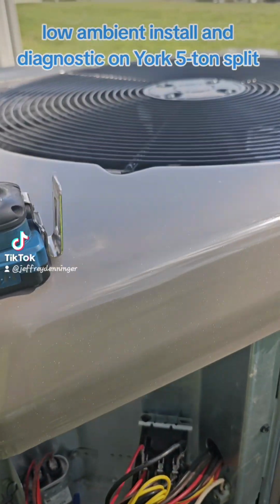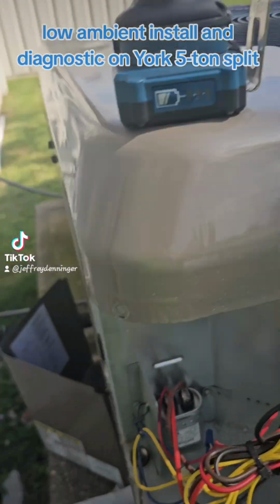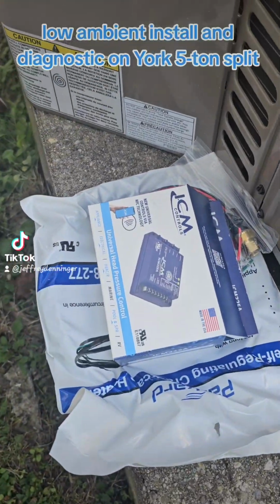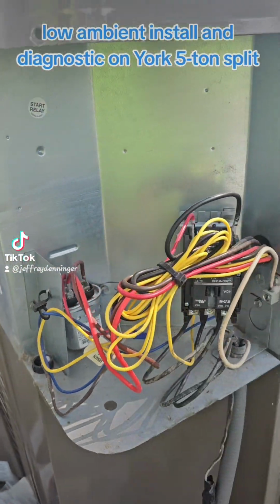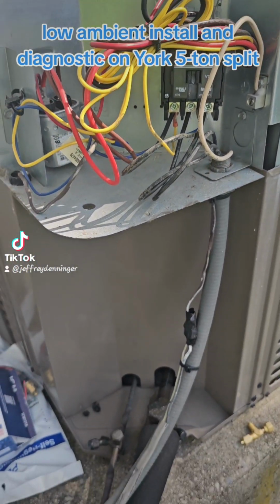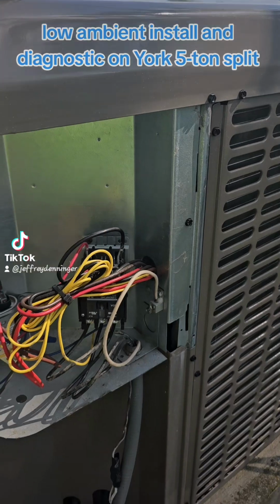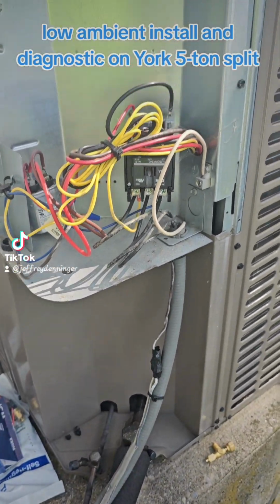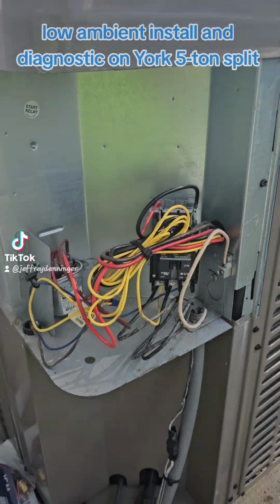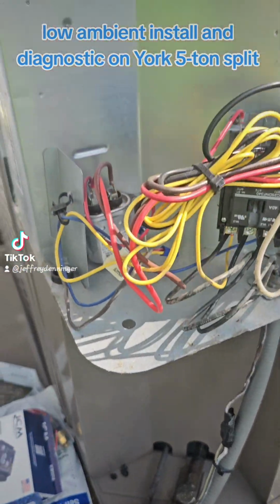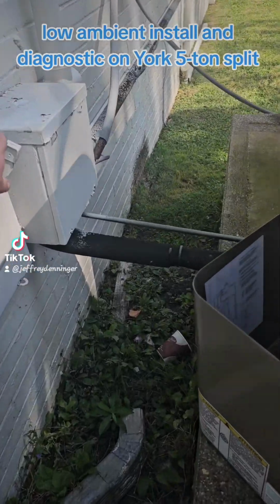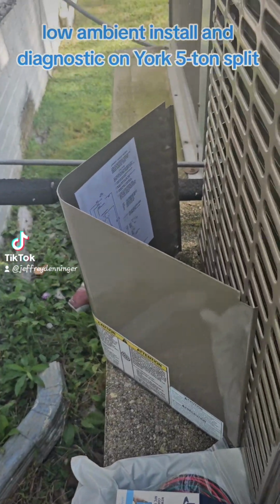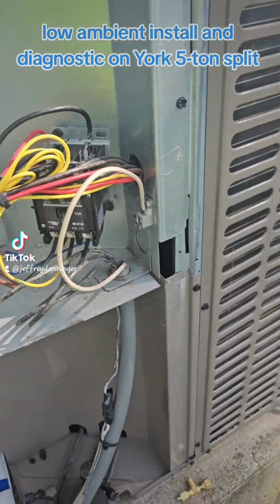Okay, today we are taking this outdoor condensing unit and we are installing a low ambient kit in it so that the customer can use it when it's cooler outside in the evenings and not freeze up the coil like they did the other day. So first thing I'm going to do is shut the unit off. I've taken the cover off.